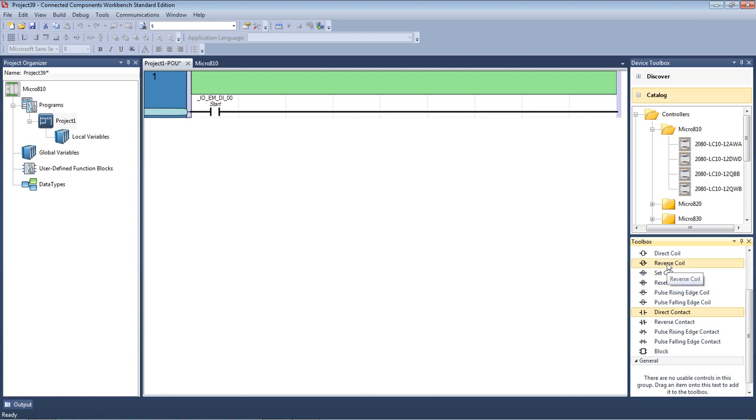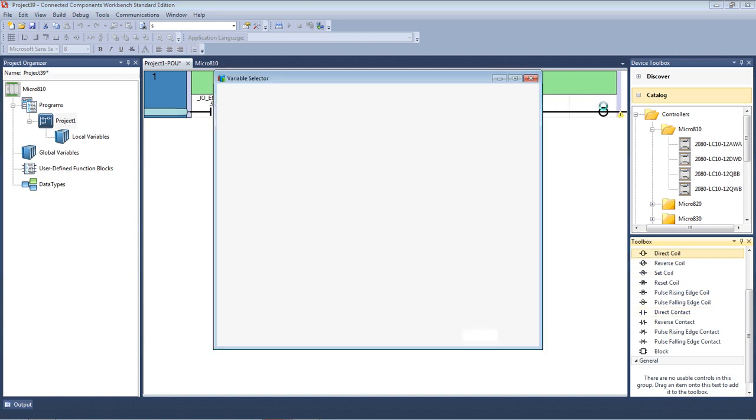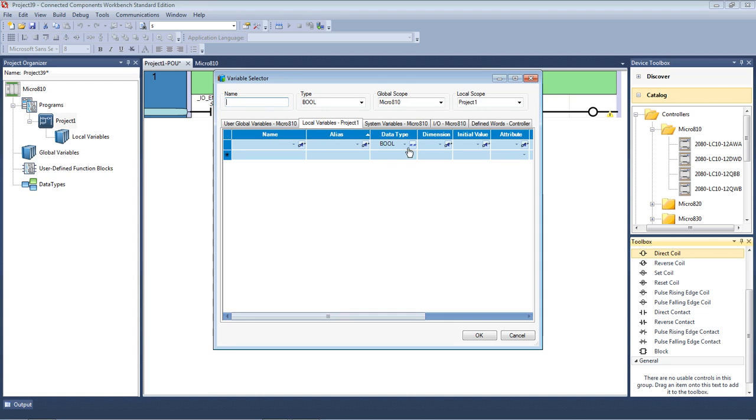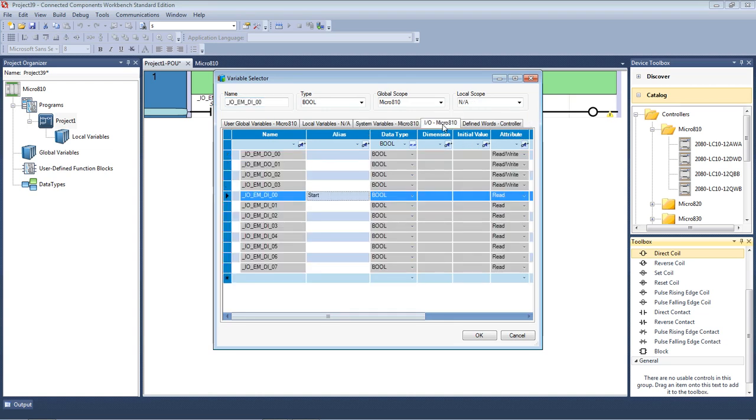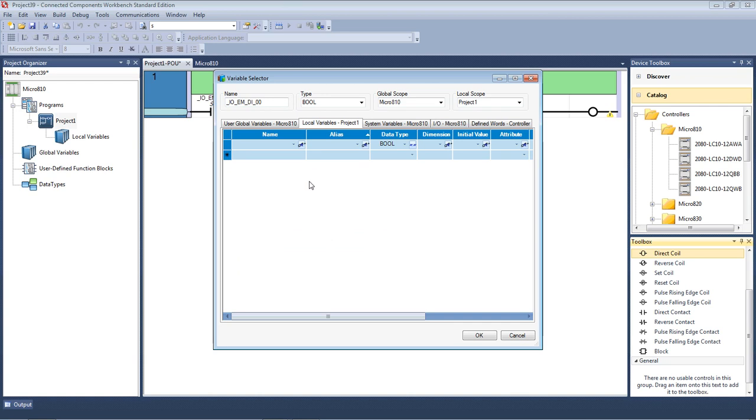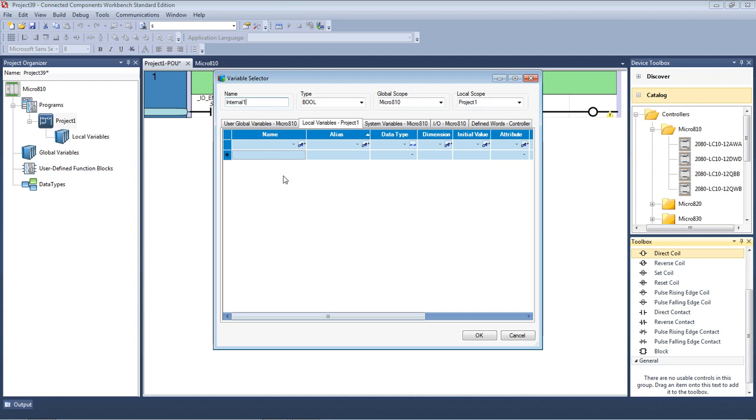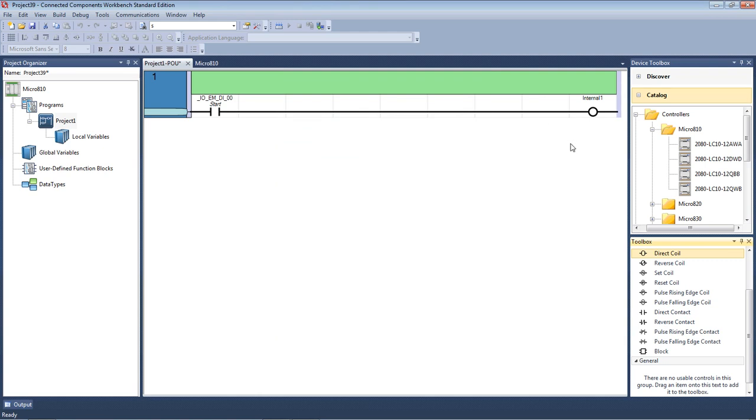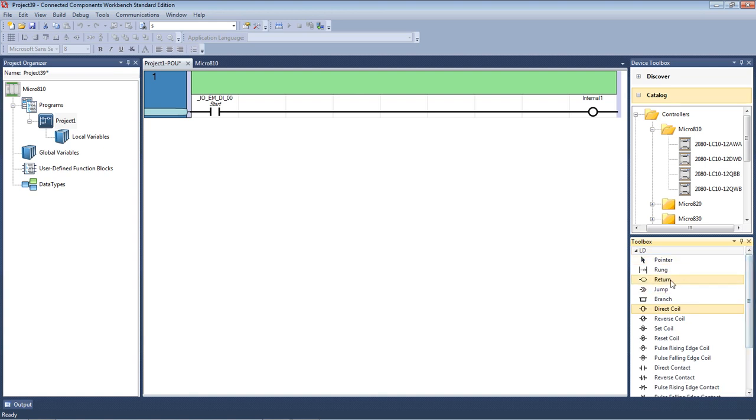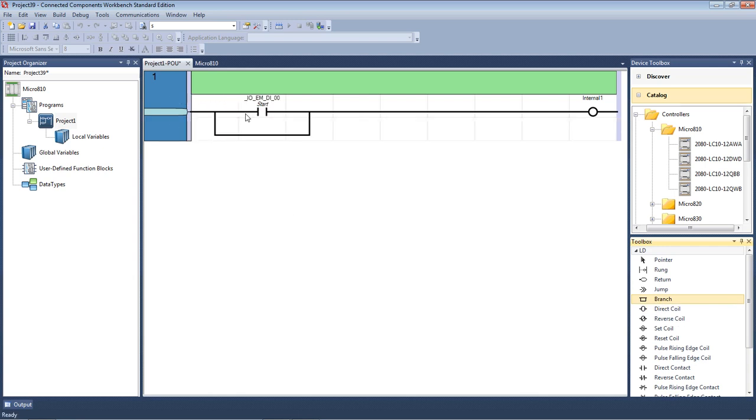Let's put a coil, a direct coil, so I'll drag a coil up to here and drop that in. Now, I could use any of my outputs here, but normally, usually when you're programming, we use what we call internal relays. By using internal relays, we're not wasting our physical outputs. So I'm just going to call this internal one, so that's just my internal relay. Now, I'm going to drag across a branch. So I'm going to drag this branch over here, drop it on top, and it gives me my parallel branch there. Because what I'll do, I'm going to set up a start-stop function here, I'll need a hold in contact.